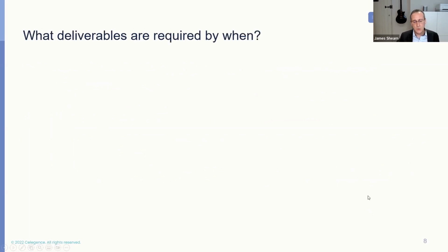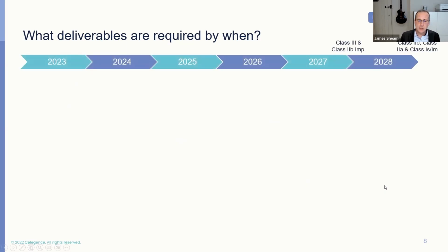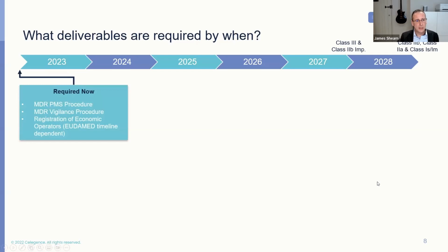So let's take a look at what deliverables would be required by when under this proposed amendment. If we look at our timeline going between now and 2028, recognizing that the deadline is different for different class devices. So for Class 3s and Class 2B implantables, that deadline is the end of 2027, and for everything else, it's end of 2028. So as we talked about earlier, we are required to have MDR compliant processes for post-market surveillance and for vigilance now, along with meeting the requirements for registration of economic operators, and that's obviously dependent upon the timeline for EUDAMED.